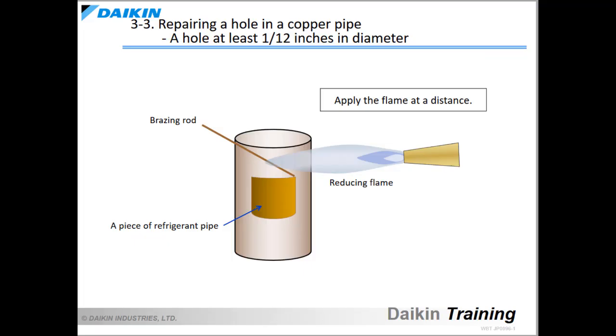When a hole is at least 1/12 inches in diameter, use a piece of copper sheet to cover it. This copper sheet can be obtained simply by cutting it from spare refrigerant piping available nearby. First, put the copper sheet on the hole. Light the torch and adjust the flame intensity. Use the reducing flame. If a piece of copper sheet comes into direct contact with the flame, it can become molten or blown away by the flame because it is thin and light. Apply the flame at a distance from the copper sheet to heat it. After the copper pipe is heated to the appropriate temperature, distribute the brazing filler metal into the gap between the copper sheet and copper pipe to cover the hole.